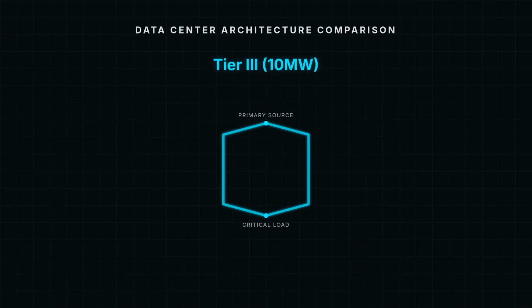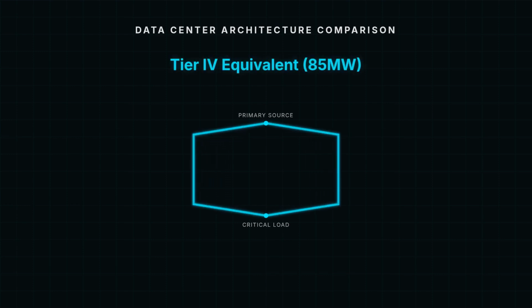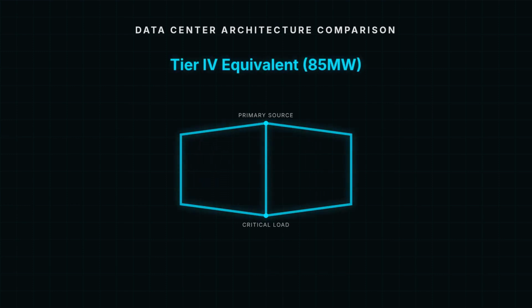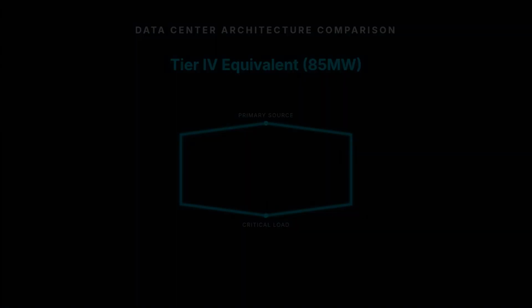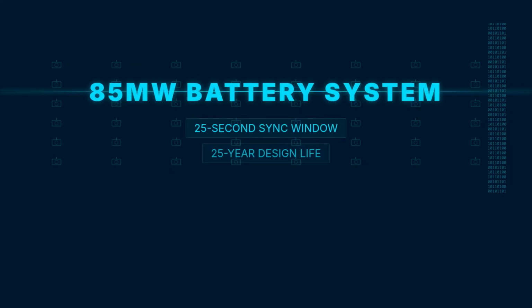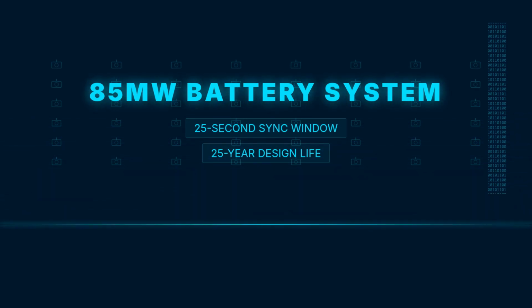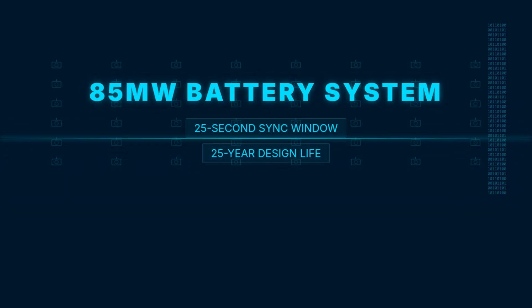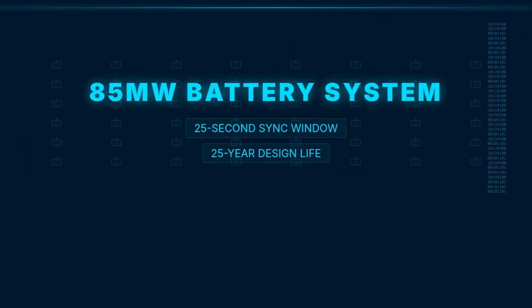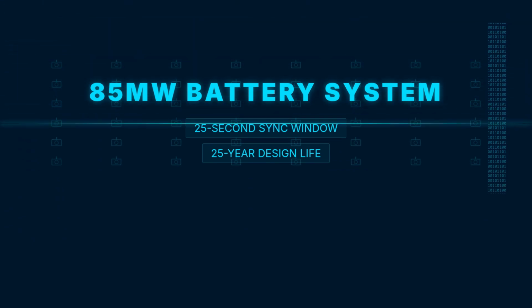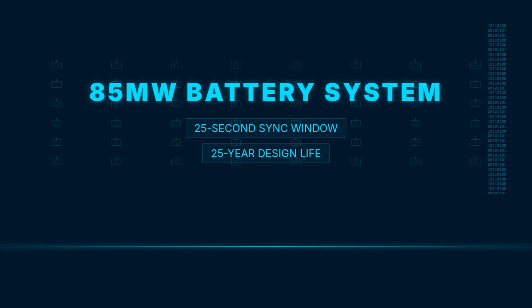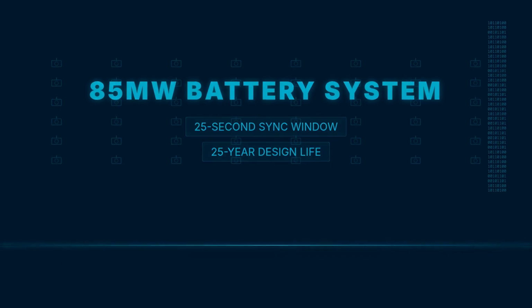We are managing 85 megawatts of critical IT load. This requires a 2N+1 architecture, two complete distribution paths plus a third, redundant string for absolute resilience. In this environment, downtime is not an option. The battery system is our bridge. It must support 20 generators through their 25-second start and synchronization sequence at a full 85 megawatt load for every single grid failure over the next 25 years. That is a lifetime of reliable performance.